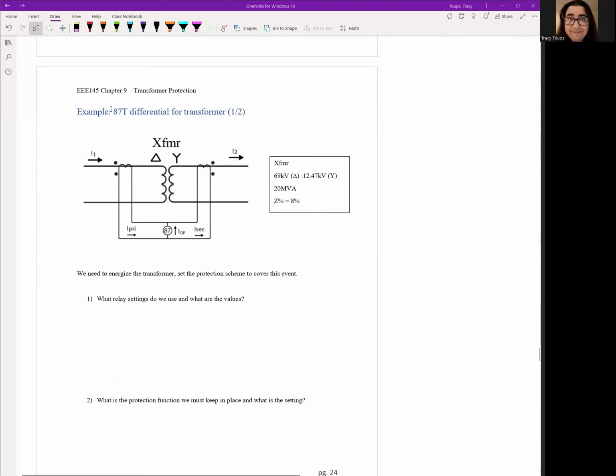Okay. So let's go ahead and take our 15, 20-minute breaks as we covered a lot. Three topics, very complicated. And so let's do a quick example to kind of rehash the settings and when to use these for which individual phenomenon. So here we got an 87T differential transformer. It's kind of similar to what we did last time, but different relay settings. So number 1, we need to energize the transformer, set the protection scheme to cover this event so the 87 relay does not trip. So what relay settings do we use? What are the values for them?